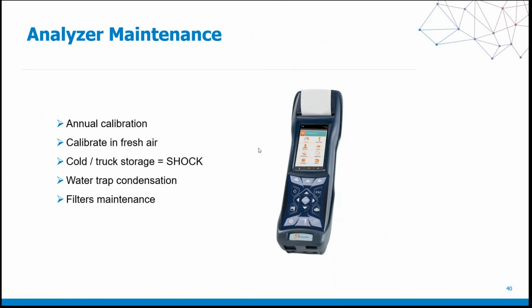You always want to turn your analyzer on outside in fresh air with no probes or hoses attached. Very important, because you want to establish a proper baseline. If you don't do that, for example, and you turn it on inside, you might already have 100 ppm of carbon monoxide inside of a space, but you're not going to know it, because if you turn it on inside, it's still going to give you your 20.9% oxygen, your 0 CO2, and your 0 CO.